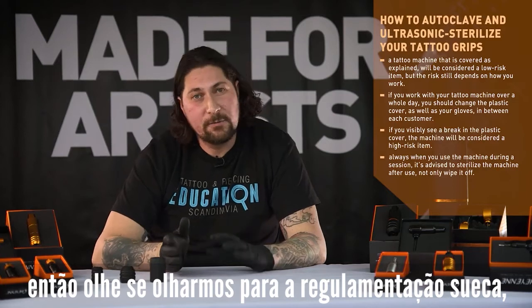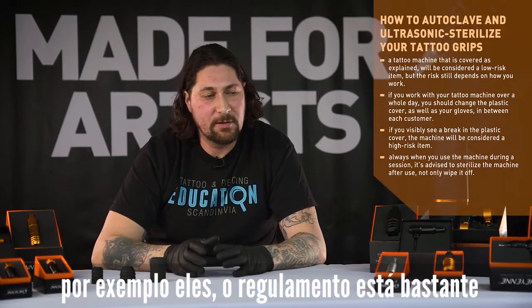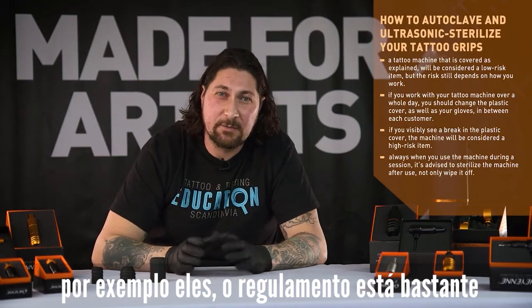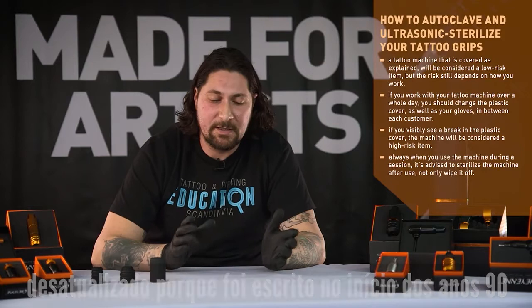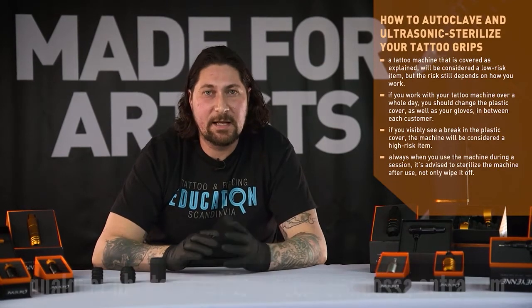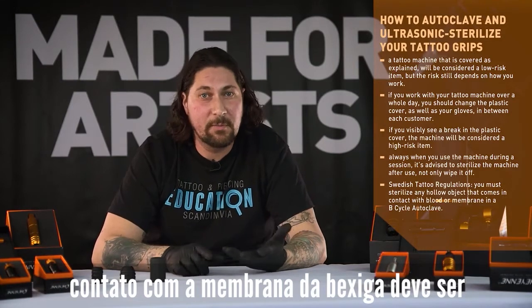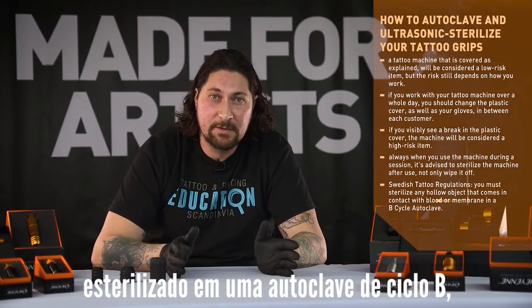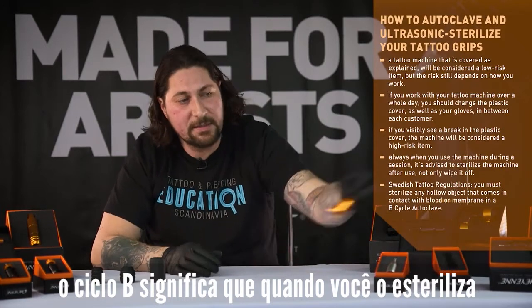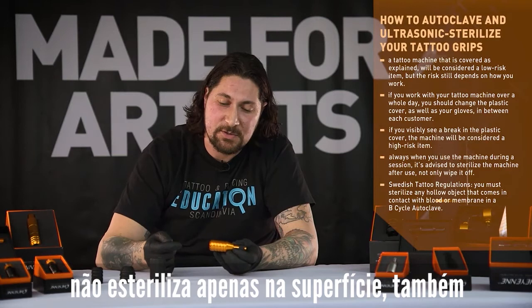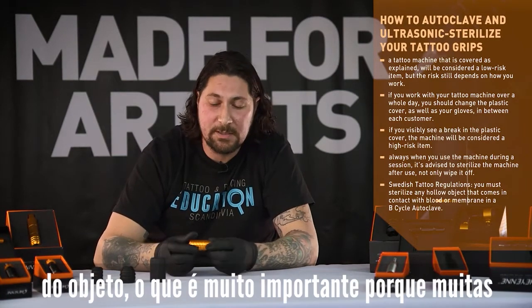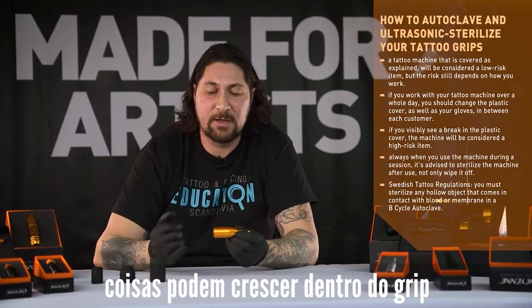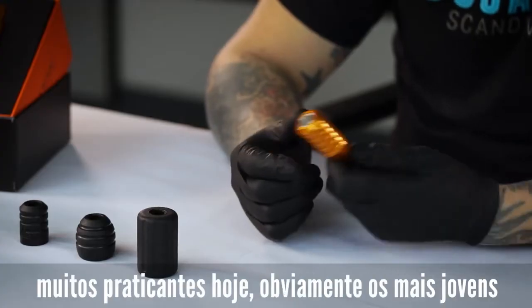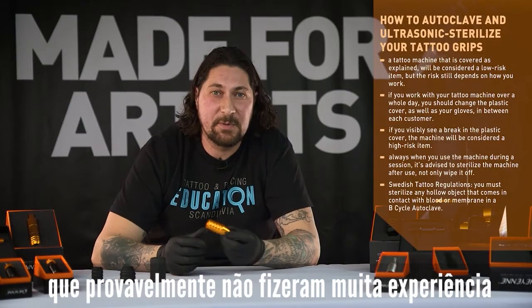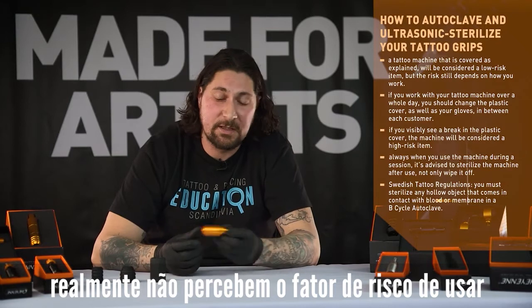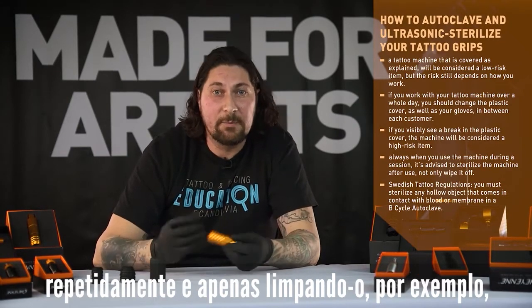So if we look at the Swedish regulation, for example, the Swedish regulation is quite outdated. It was written in the early 90s, it's still in use. And that guideline says that any hollow object that can come in contact with blood or membrane should be sterilized in a B-cycle autoclave. A B-cycle means that when you sterilize it, it doesn't only sterilize on the surface, it also sterilizes inside the hollow object, which is very important because a lot of stuff can grow inside the grip. Many practitioners today, obviously the younger ones that probably haven't that much experience, don't really realize the risk factor of using it over and over again and only wiping it off, for example.